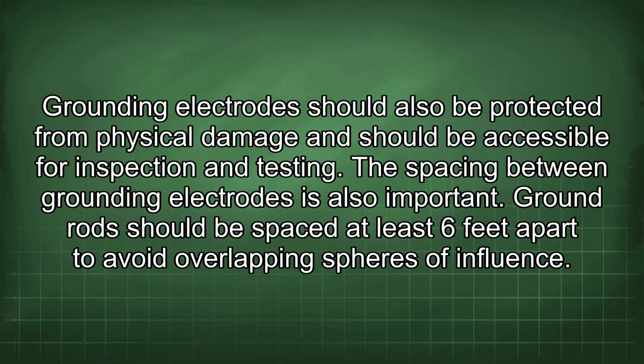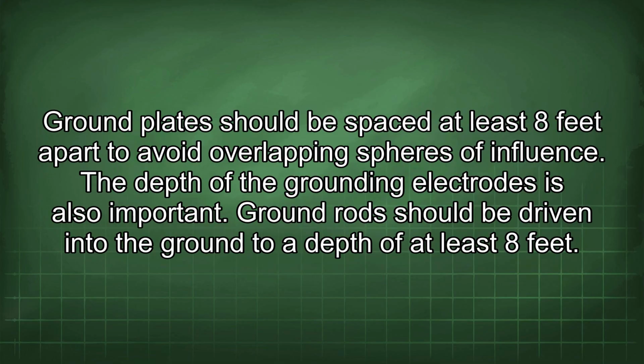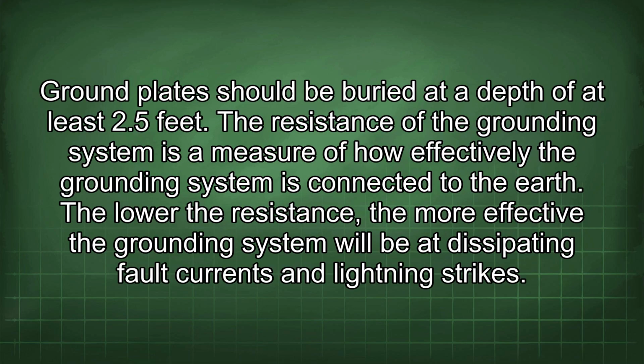The spacing between grounding electrodes is also important. Ground rods should be spaced at least 6 feet apart to avoid overlapping spheres of influence. Ground plates should be spaced at least 8 feet apart to avoid overlapping spheres of influence. The depth of the grounding electrodes is also important. Ground rods should be driven into the ground to a depth of at least 8 feet. Ground plates should be buried at a depth of at least 2.5 feet.